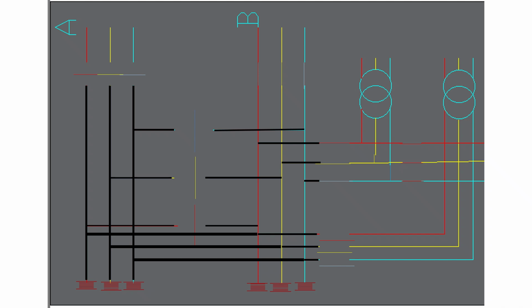The facility is the neutral section. Neutral section is provided in front of the TSS so as not to bridge the two transformer outputs. There is a phase difference. Here I have shown a three phase output. It is not for railway, because in railway it will not be three phase. For Scott connection, two outputs, one from each transformer, will come out, and in open delta one transformer feeds one side and another transformer feeds the other side, but it is also two terminals, not three. I have shown three here because it is not for railway, it is to give you a simple idea.